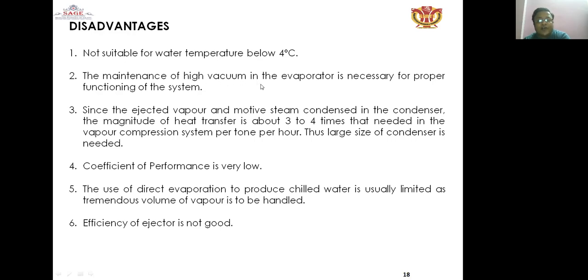The maintenance of high vacuum in the evaporator is necessary for proper functioning of the system. Since the ejected vapor and the motive steam condense in the condenser, the magnitude of heat transfer is about 3 to 4 times that needed in the vapor compression system per ton per hour. Thus, a large size of condenser is needed. Coefficient of performance is very low.